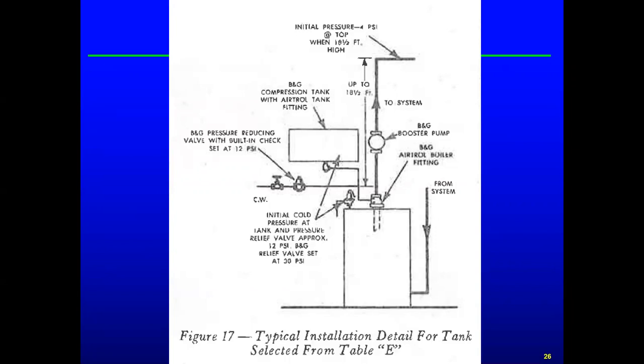This fitting is designed to separate out those air bubbles and send them over to the compression tank. What could happen if these bubbles circulate through the pump and out to the system that would be detrimental? Cavitation is where the fluid you're pumping gets to or below the vapor pressure at its temperature, and it actually boils. They are gas bubbles in there, so they could contribute and hurt the pump a little bit if there was a lot of them. Out in the system, why do you not want air circulating? Why do we have to control air in all of this?